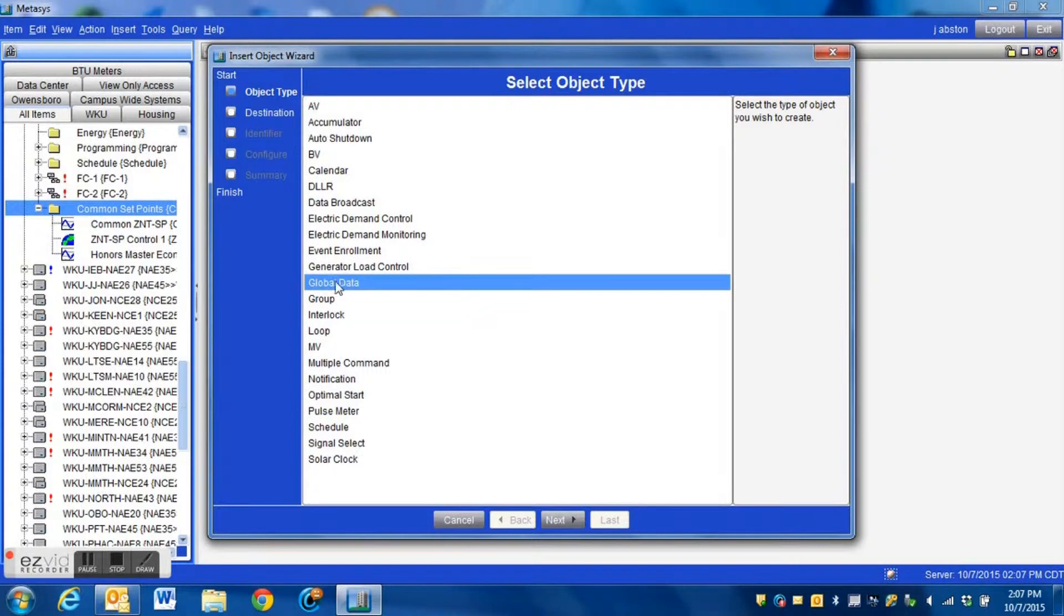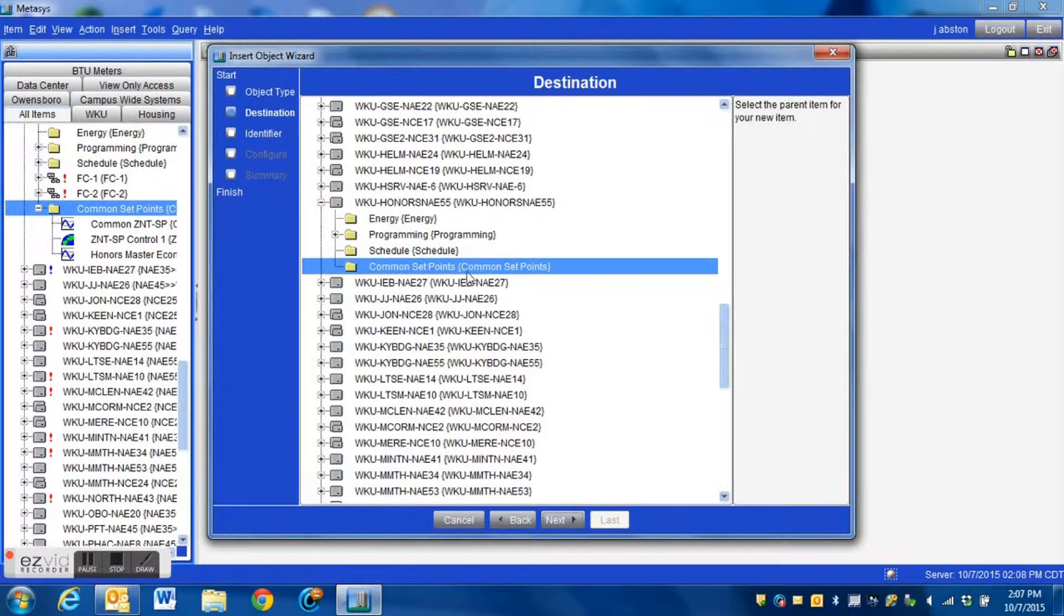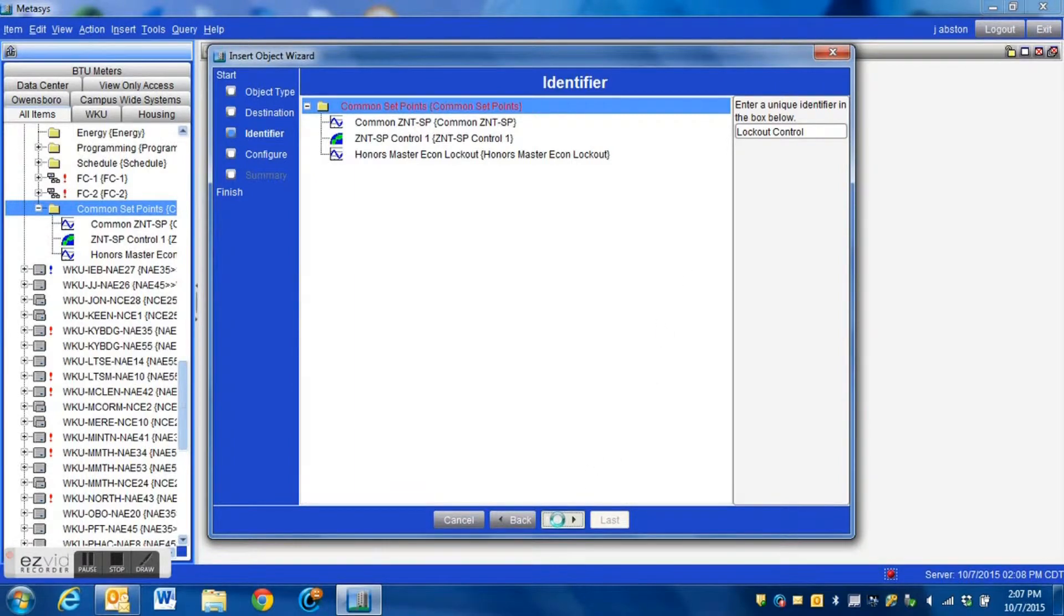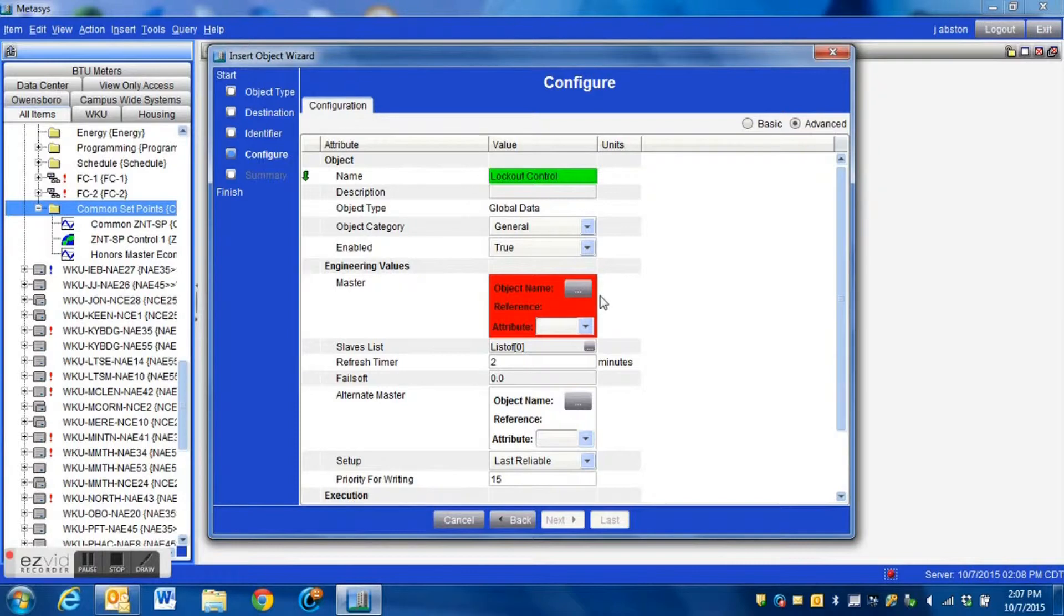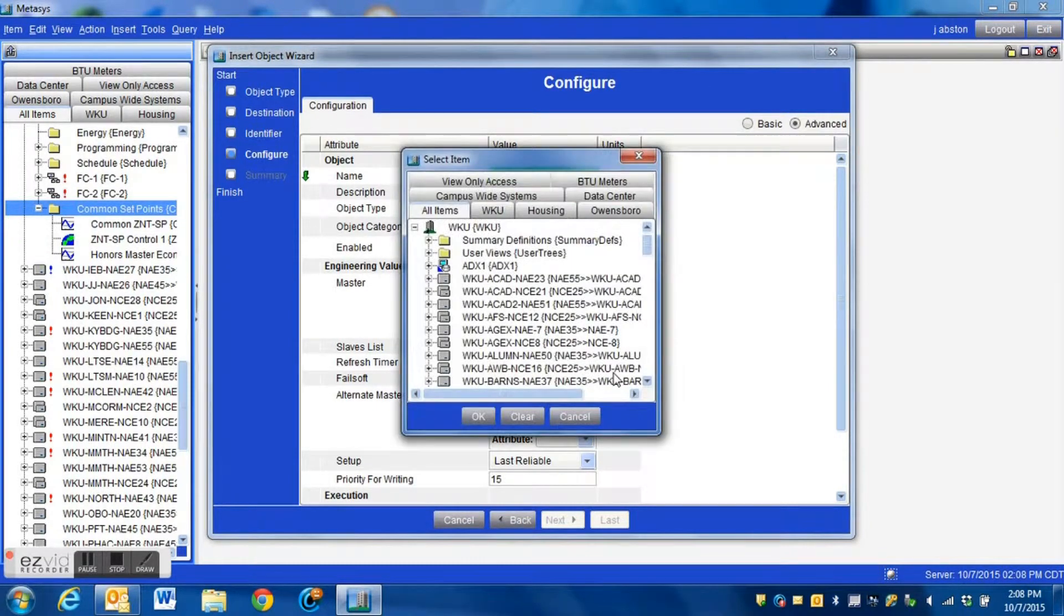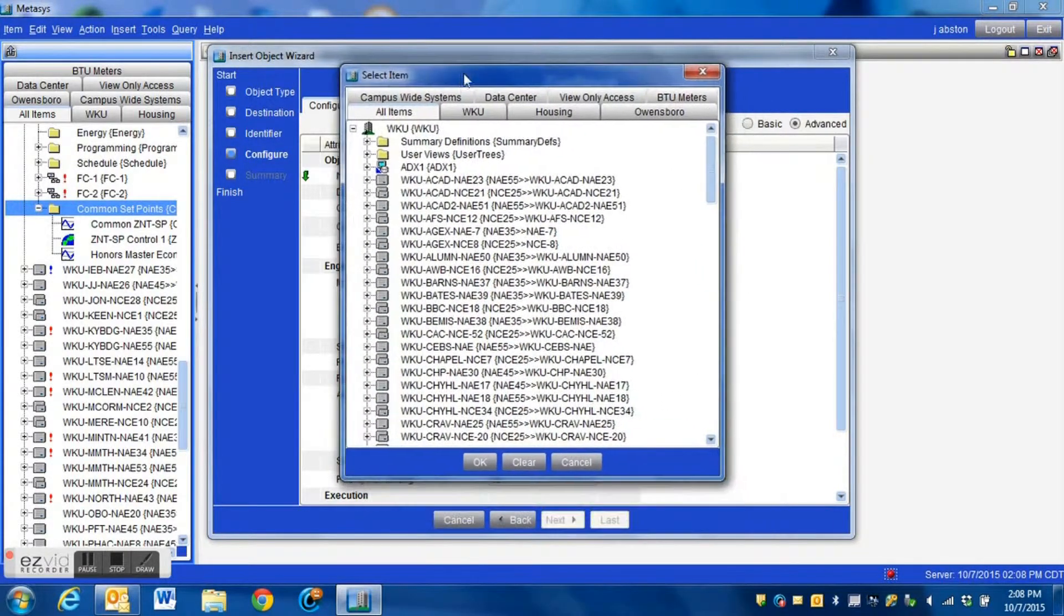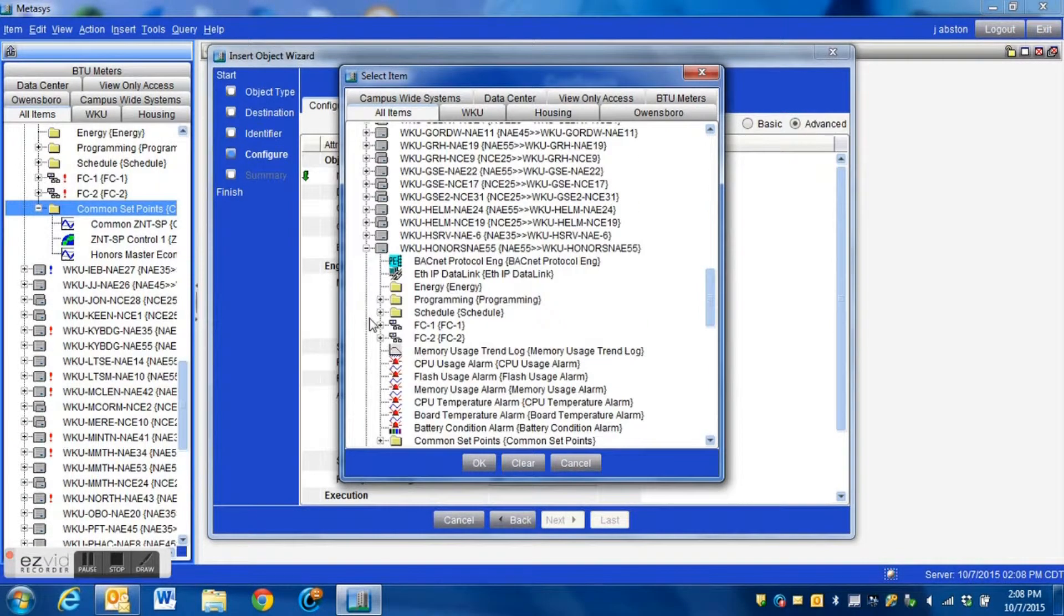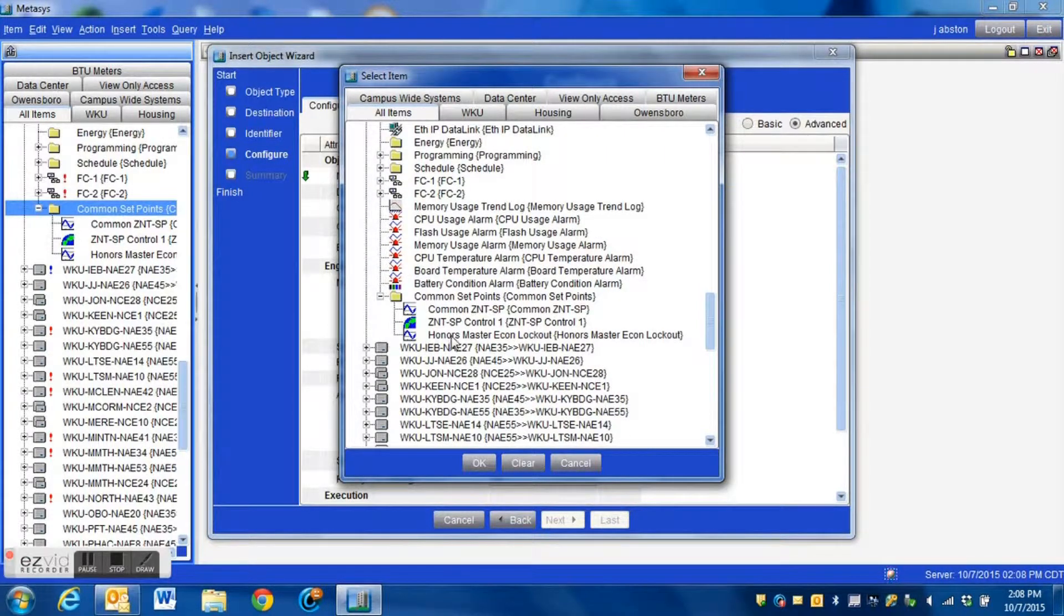Once we have that highlighted we hit next and it's going to ask us the location where we want to put this. We will keep this in the same folder and here we will simply give it a name, something recognizable that will identify it with that setpoint. We hit next and in this screen here you'll notice in the middle of the screen that big red block. That is the value that the logic block references to and what we have to do here is link that to the point which we created. We hit the little gray box and then we go back into our tree and simply select the analog value which we created just a few moments ago.